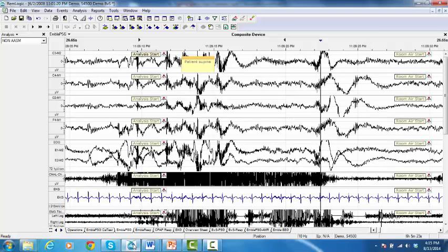In this video, I'm going to demonstrate how to run the automatic analysis for a PSG recording. Before starting with the automatic analysis, mark the appropriate time of analysis by inserting lights off, lights on, analysis start, and analysis stop events. And if it is a split night, you will also need to mark pressure start, optimal pressure start, optimal pressure stop, and pressure stop into the recording.